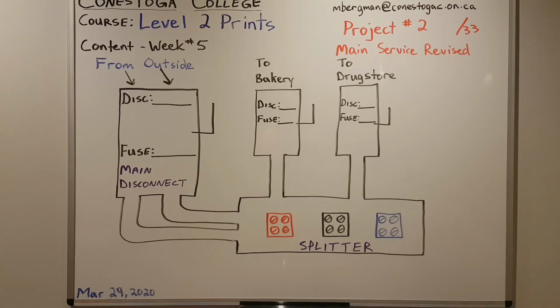So you have to tell me what size the disconnect will be, what size fuses will go in the disconnect for the bakery, and remember, it's 600 volts. From the bakery's disconnect in the main electrical room, we have to go to the bakery, so you have to tell me how long that conduit is, what size that conduit is, what size the disconnect is, and what size the fuses are. The same goes for the drugstore.